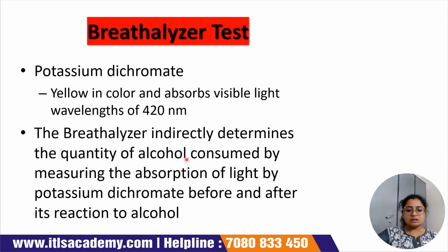So the breath analyzer will indirectly determine the quantity of alcohol consumed by measuring the absorption of light by potassium dichromate before and after its reaction with alcohol. Before its reaction with alcohol, it will be intact, it will not be destroyed, isn't it? But after its reaction with alcohol, it will be converted. So that will give you the result. You don't have to compare, the machine itself will compare and give you the result. If there is any difference, then it's positive, and if there is no difference in the light absorption or in the reading of the spectrometer, then there is no alcohol present.